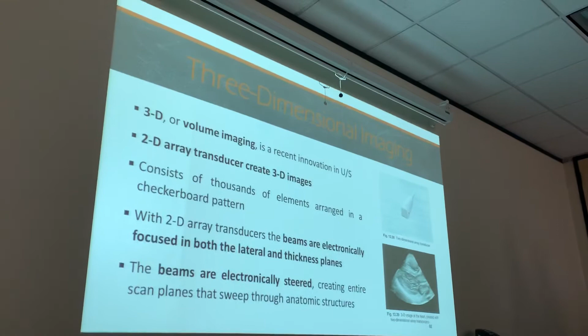Transducers, beams are electronically focused in both the lateral and thickness planes. Okay? So that means if they're electronically focused, not only are the signals arranged in a curve in the width plane, they are also arranged in a curve in the height plane. Correct? Because that's what focusing is, having that curved electrical spike sent to the elements at one time. The beams are also electronically steered, creating entire scan planes that sweep through the anatomic structures.